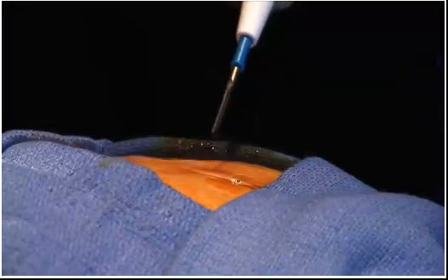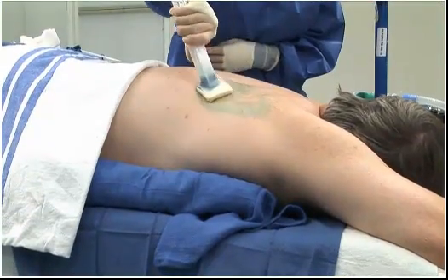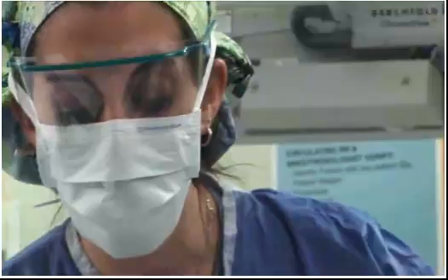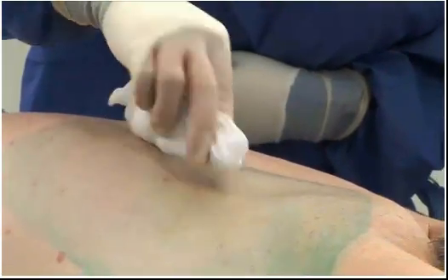Like oxygen-enriched fires, alcohol-related fires can cause serious injury. Alcohol-based prep solutions burn readily in room air, and the fires are hard to see. If you use a prep solution containing alcohol, it must be allowed to dry completely before draping. The same holds true for any tinctures or flammable dressings, such as collodion — they must be allowed to dry before use of an electrosurgical pencil or other ignition source near them.